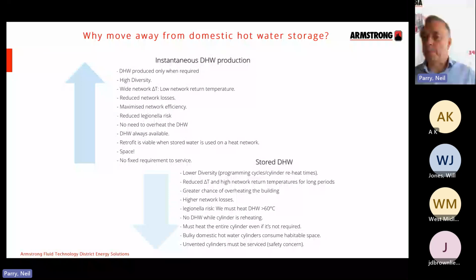But what we need to remember is as soon as you store domestic hot water, you have the potential for Legionella growth, so we need to store it or at least cycle it above 60 degrees C every now and then, and of course that needs a lot of additional energy to do so. Energy that you don't need if you're generating instantaneously. And of course, when that cylinder is starting to get up to temperature, your return temperature on your network is going to be significantly higher than it would be with instantaneous.